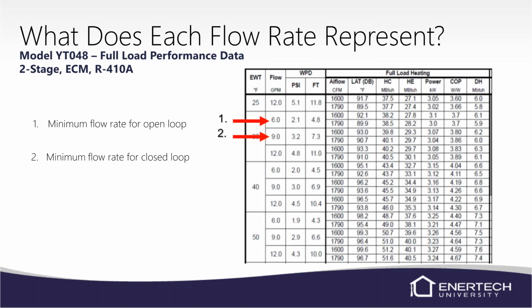The next flow rate is a minimum flow rate for a closed loop. We can go down, if we have to, down to 2.25 GPM per ton. That's the minimum we can go. We would prefer you're at 3, but if you're at the edge of a pump curve and you don't want to add another pump and you can get 2.25 GPM, we're okay with that. Just don't go any lower than that on a closed loop. The third flow rate is the recommended flow rate on a closed loop, so 3 GPM per ton. So that's what we're looking at on our flow rates.